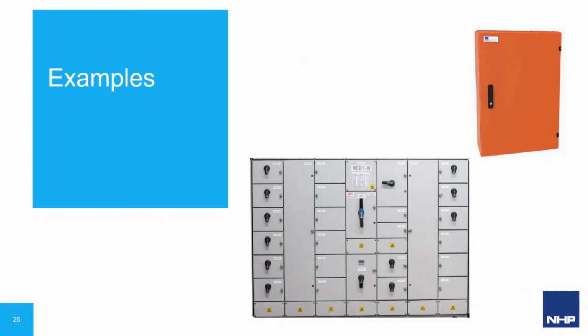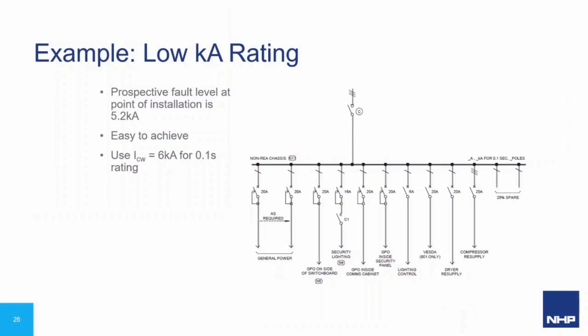Now we'll have a quick look at some example single line diagrams and how requesting different withstand ratings will impact their design. We'll start with the example where the kA rating is quite low. The prospective fault level at the point of installation is stated to be 5.2 kA. This is straightforward and is easy to achieve. There is no point using a conditional rating here. A typical offer would be an ICW of 6 kA for 0.1 seconds to enable us to use miniature circuit breakers without considering the upstream protection.